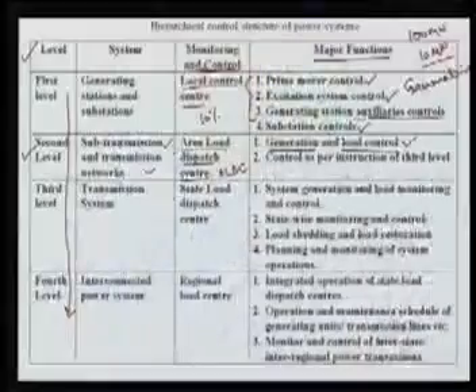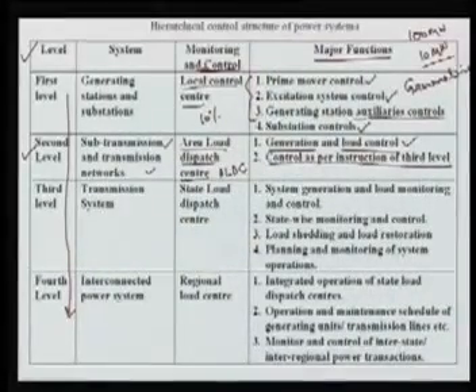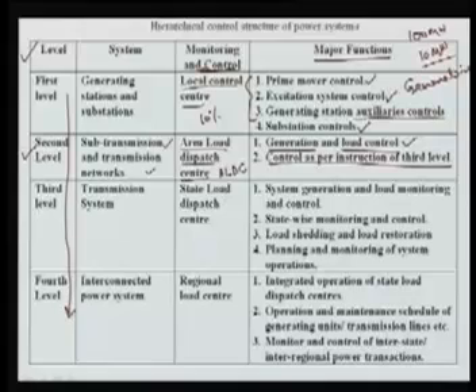And also they get control as per instruction of the third level. Now this is the third level control, meaning the state load dispatch centers. They give some information. For example, if there is some line between, let's suppose, one station and another station, and they get the information to trip this line, then sitting in the control room, they can trip that line. Again, the requirement for why this line is to be tripped comes from the third level. So the third level control is nothing but your state load dispatch center, and it is also called SLDC.